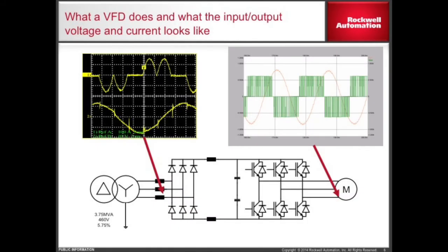Below is a typical AC drive power structure. To the left is shown a delta Y transformer with a Y secondary and a solidly grounded neutral. To the right is a diode bridge which rectifies the three-phase utility power into a DC voltage. To the right of the diode bridge is a DC link choke and bus capacitors. To the right side of the screen, the output transistors are shown, which create the PWM signal that provides power to the AC motor. The oscilloscope picture shown below shows the PWM voltage and sinusoidal AC current waveform seen by the motor.